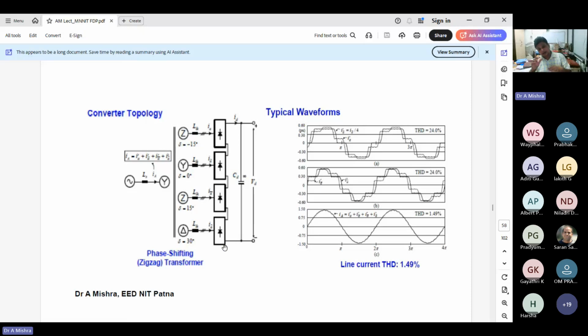Independent 6 pulse converters are connected in such a way through the phase shifting transformer that it produces a 24 pulse output. A 24 pulse converter is not something new. It is the combination of 4 six pulse converters connected with the help of the phase shifting transformer with the appropriate phase shift provided, and then the output is combined together to get the 24 pulse output. You can see the line current THD is 1.49%.